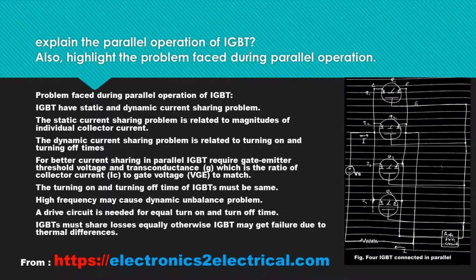For better current sharing, parallel IGBTs require gate-emitter threshold voltage and transconductance G, which is the ratio of collector current IC to gate voltage VGE, to match. The turning on and turning off times of IGBTs must be the same. High frequency may cause dynamic unbalance problems. A drive circuit is needed for equal turn-on and turn-off time. IGBTs must share losses equally, otherwise an IGBT may fail due to thermal differences.